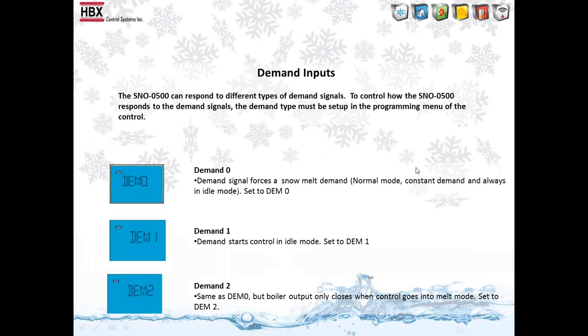The demand input. So these three parameters are probably, if I was to pick three parameters that are the most confusing on the control, it would be these. So what this allows you to do, the demand input. So we have a demand input on the Snow500 that can do a few different things when you're in the different modes. So when you're in demand 0 mode, basically you're going to always be in idle unless you're in warm weather or cold weather shutdown. So what that allows you to do is it frees up that demand terminal for a forced melt demand.